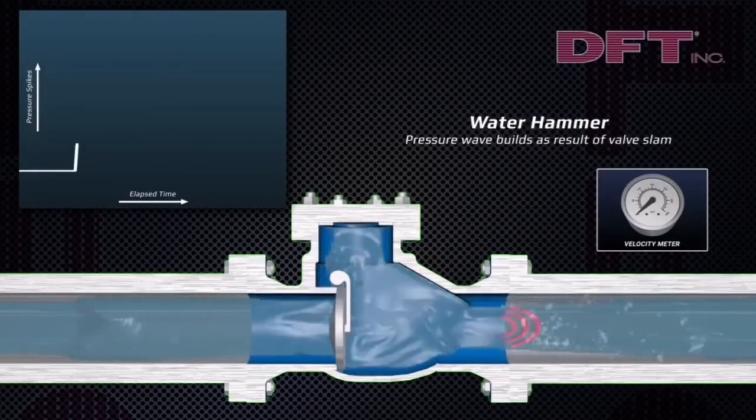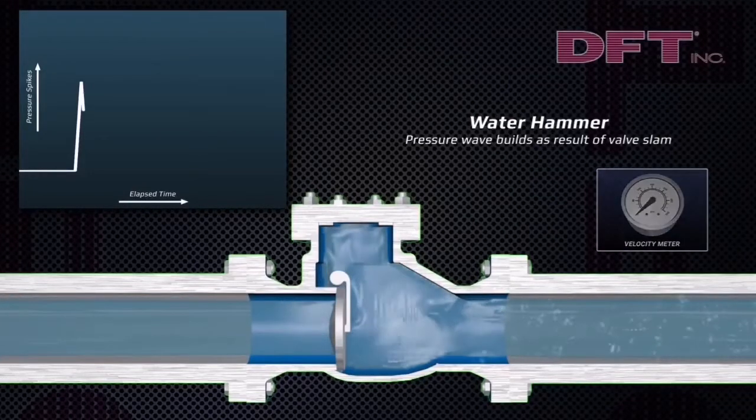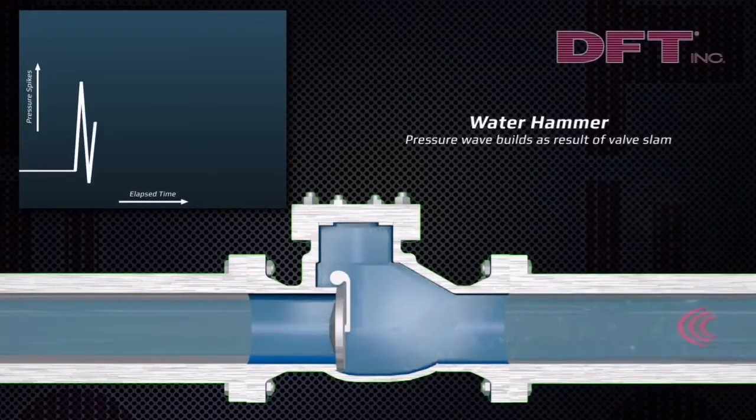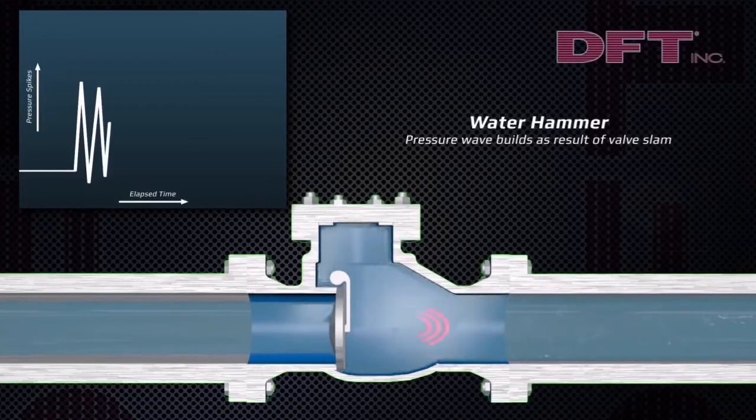When the pump shuts down, it is gravity and reverse flow that closes or slams the swing check valve closed, resulting in pressure wave build and water hammer.